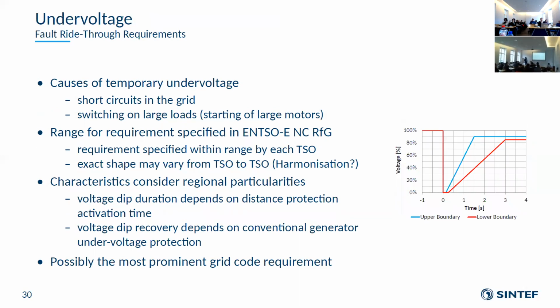This fault ride-through is mostly relevant for under voltage, as in the example. The grid codes specify curves of the shape of a voltage dip, this is 100% of voltage, with a time specification. The European grid codes give you a range between the red and the blue curve, and any single TSO could draw a line in between somehow. But the range is not so big, so even though grid codes are very different around Europe, we know pretty well what kind of voltage shape we need to withstand for a wind power plant. And if we just take the red one, we're on the safe side.